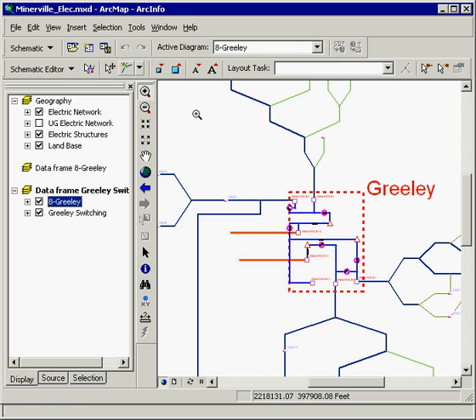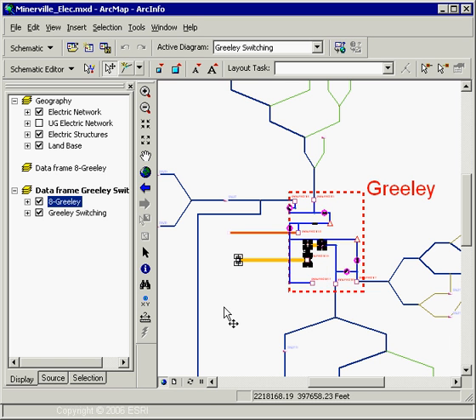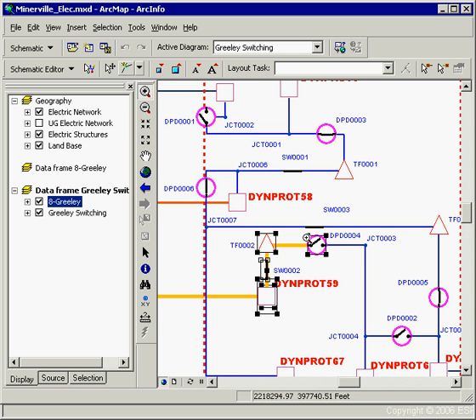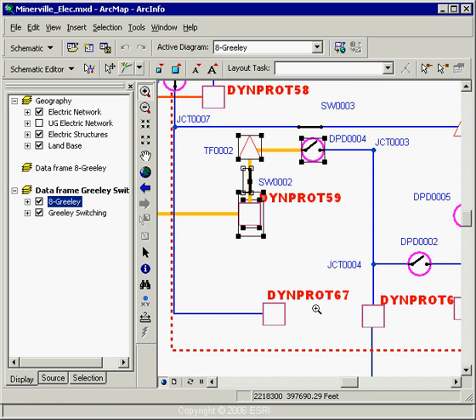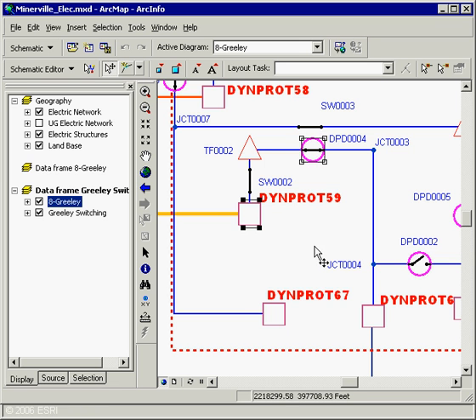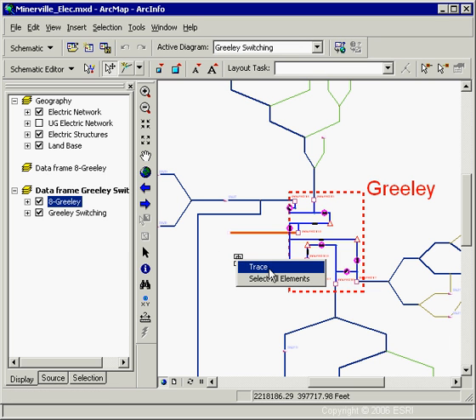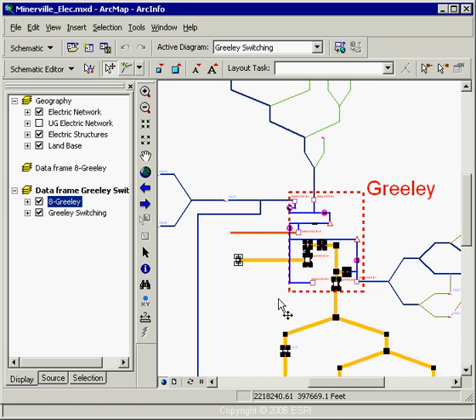Adding the Greeley inside plant drawing to the same data frame shows non-spatial and spatial data together simultaneously. For customization: I can set up tracing that goes between physical geography and non-spatial tabular data. Running a trace from the outside into the inside plant — it stops because it hits a switch in an open position blocking electricity flow. Another piece of customization allows the user to modify the switch position, updating the record in the database. Re-running the trace from the same location now shows a much different result — the trace makes it through the internal non-spatial data and back out into the spatial data.